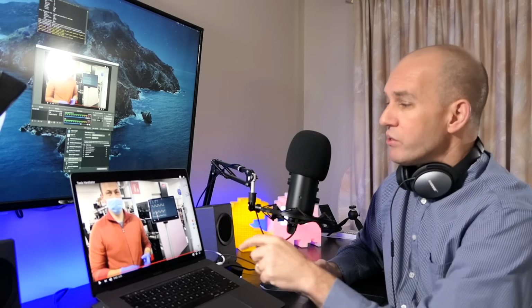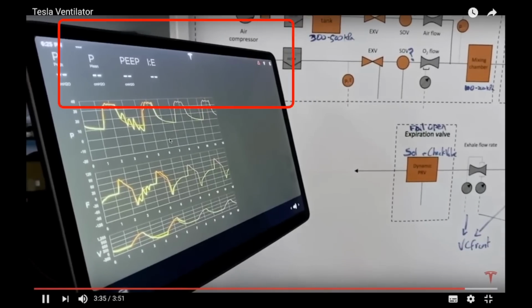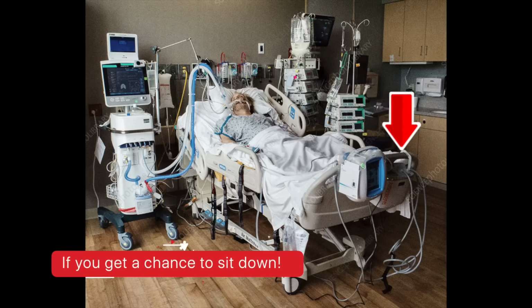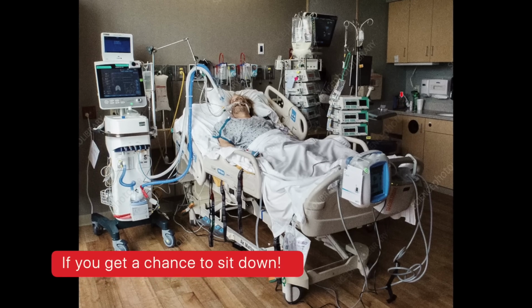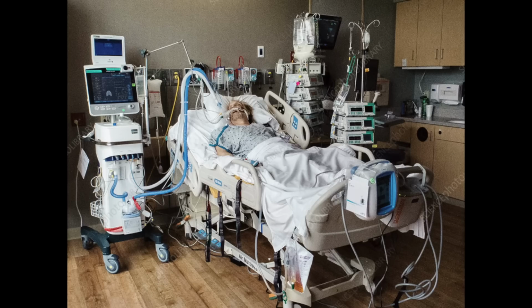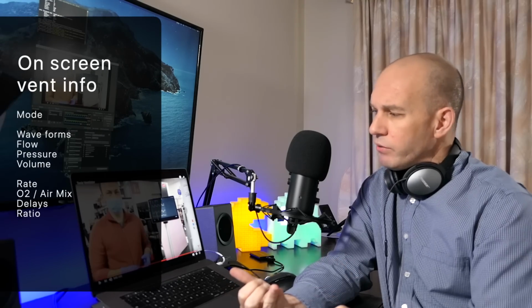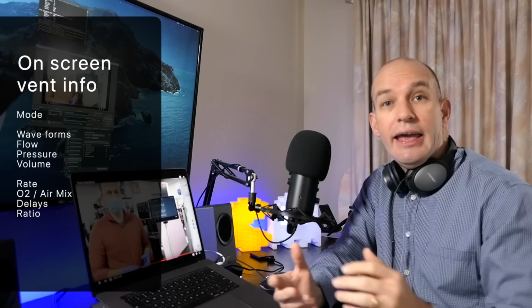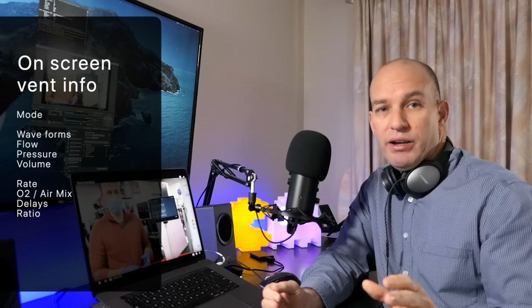My only suggestion to Tesla would be to make your numbers at the top a lot larger, to be able to see them from the end of the bed. Typically when nursing a patient on a ventilator, you'll be down by the foot end of the bed, with the head about 2.5 meters away from you and the ventilator sitting right up there. So to be able to, from a distance, eyeball what the actual settings are - your pressure, your volume, your rate, maybe the ratio, or if there's a delay set to enable the patient a longer time to expire the air that comes out of them - those sort of things need to be really large numbers. As nurses, particularly like me with bad eyes, it's good to be able to see that from a distance.